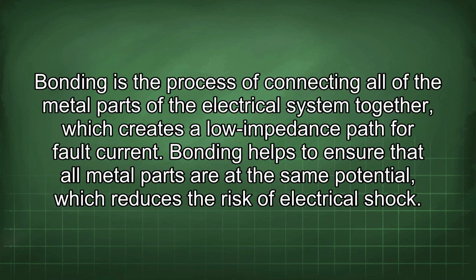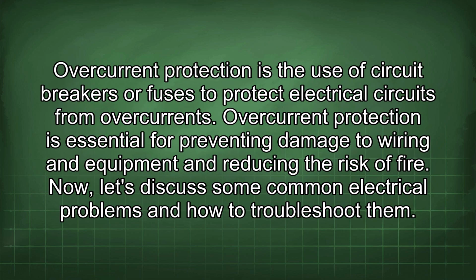Bonding is the process of connecting all of the metal parts of the electrical system together, which creates a low impedance path for fault current. Bonding helps to ensure that all metal parts are at the same potential, which reduces the risk of electrical shock. Overcurrent protection is the use of circuit breakers or fuses to protect electrical circuits from overcurrents. Overcurrent protection is essential for preventing damage to wiring and equipment and reducing the risk of fire.